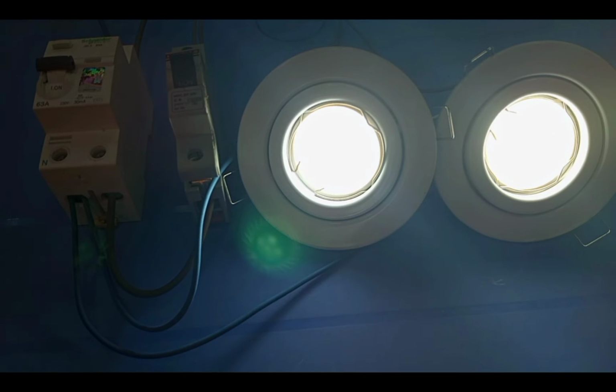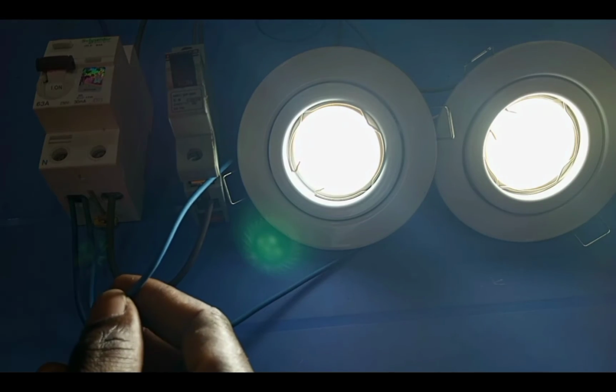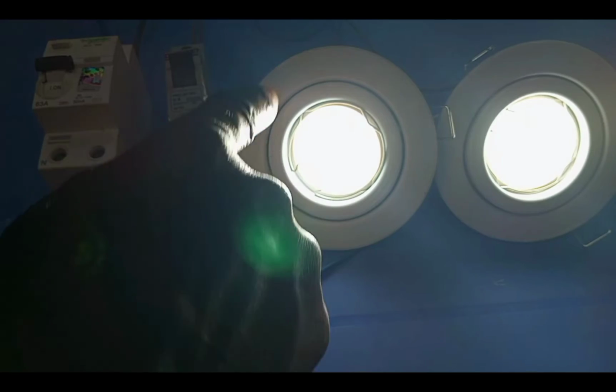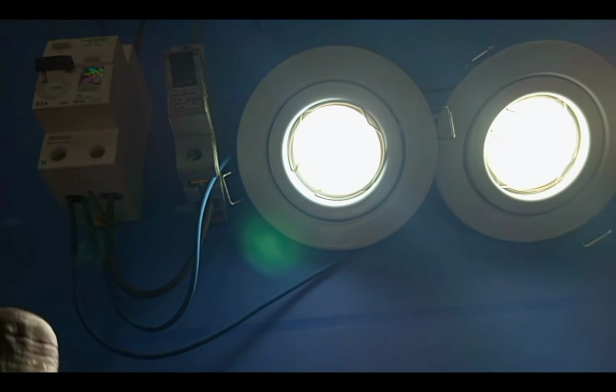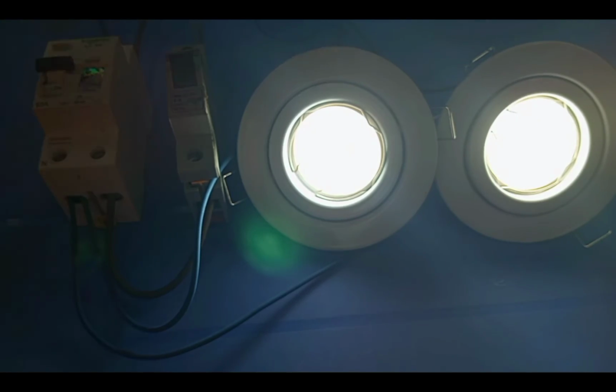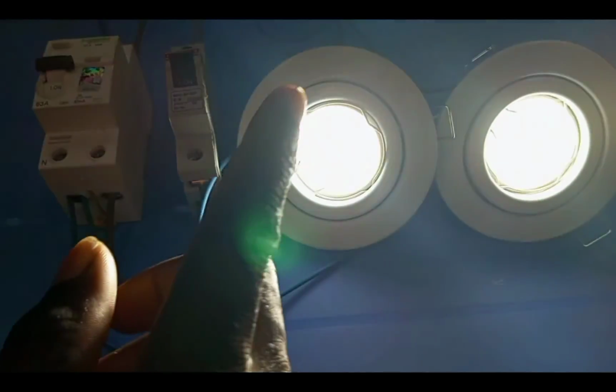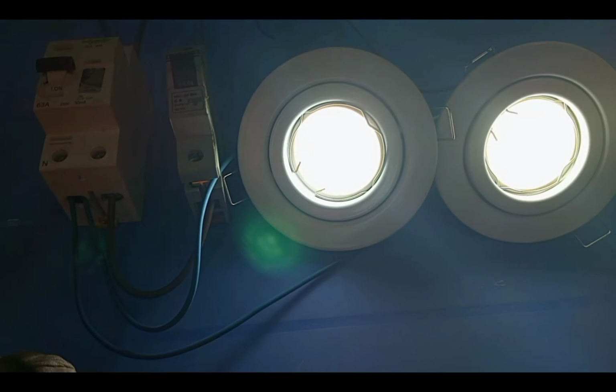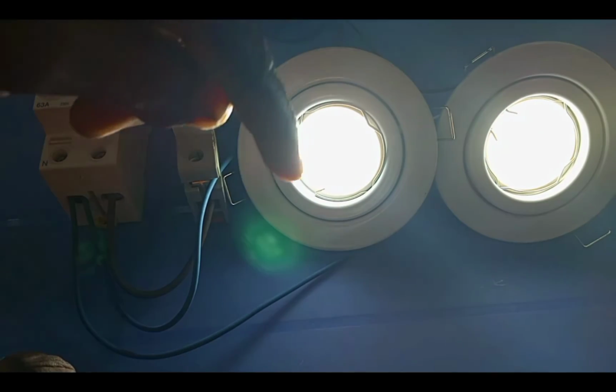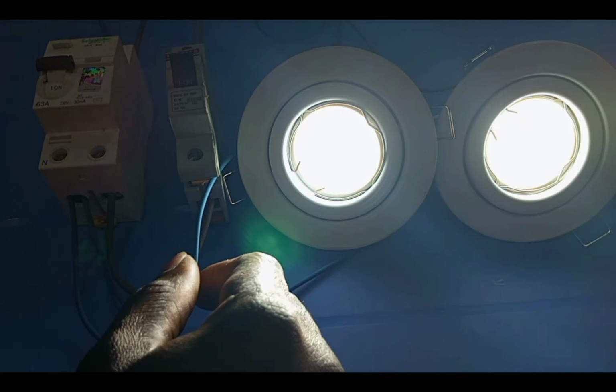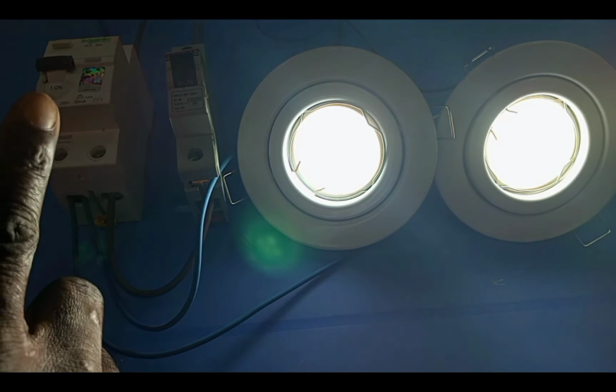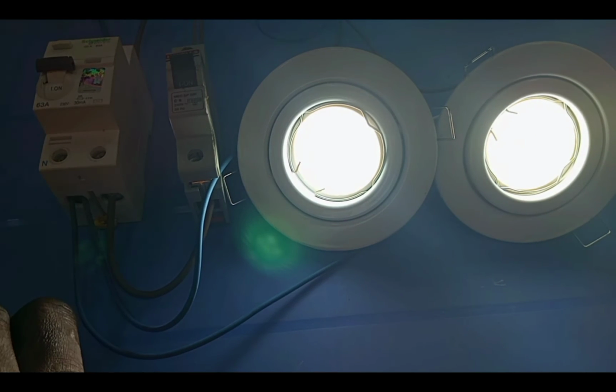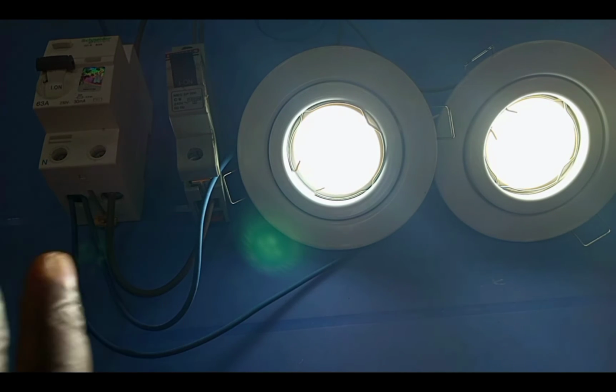When I do that, what happens is that you will have only one neutral wire here. That is the neutral coming from this particular lamp. Okay, and so what it will mean is that the live cable is supplying two lamps, but the 0.04 amps that is flowing through the live wire, when it is coming back through the neutral, it will now be 0.02. So that creates an imbalance.